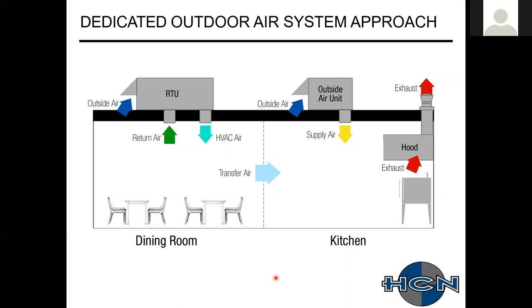The best bet for this is to talk to your owner, get the information that you can to see what will work. Because in certain situations, the traditional design may work better. The dedicated outdoor air approach has actually been used for most fast serve restaurants for a long time now, McDonald's, Wendy's, that kind of stuff. They're using just exhaust only hoods. The rooftop units are providing that outside air, and their kitchens are open. It's a nice laminar flow of air coming into the system, doing what it's supposed to do by utilizing that transfer air as much as they can.